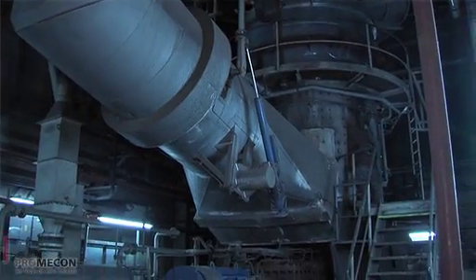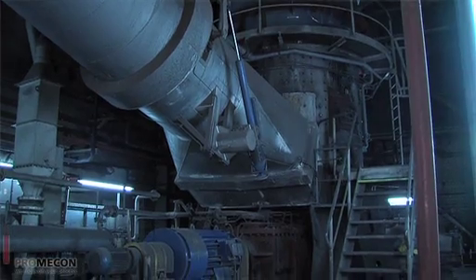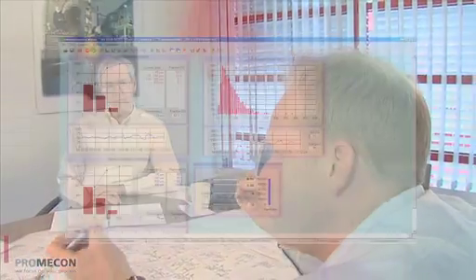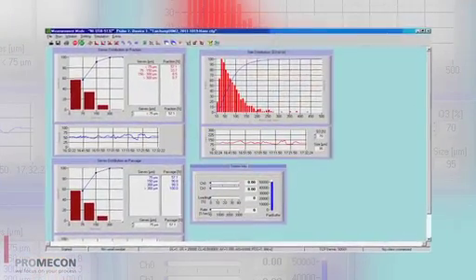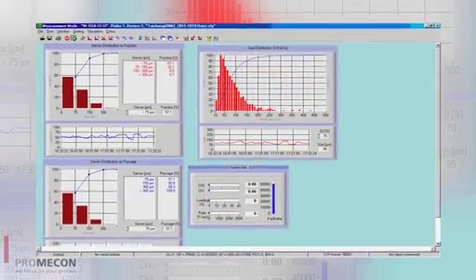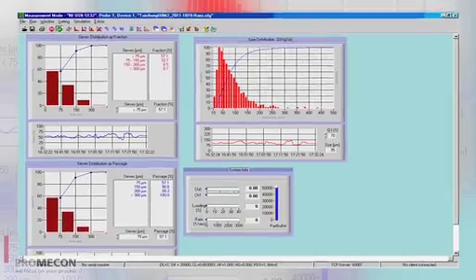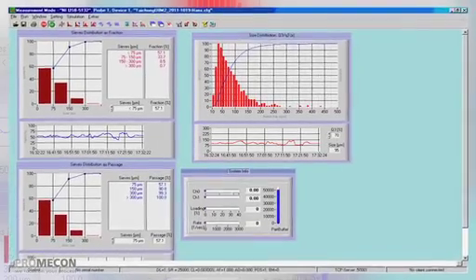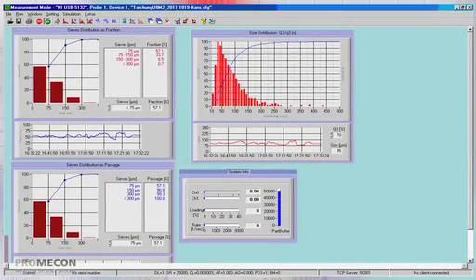Can the pulverizer do that within the limits of its design? And the third one, of course, talking about pulverization, is the fineness of the powder or pulverized fuel. The particle size distribution has an impact also on the mass flow. If you have more coarse material, you can grind more coal than if you have more fine material. So it all sticks together, and mass flow certainly is one big part of the whole equation.